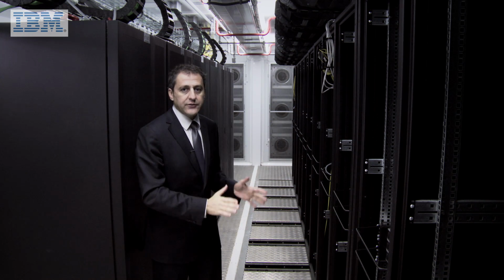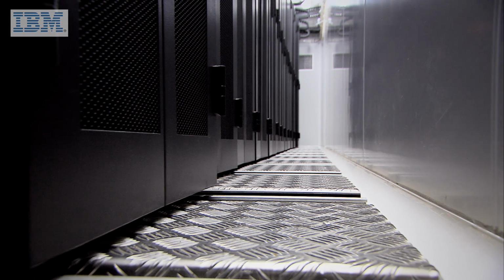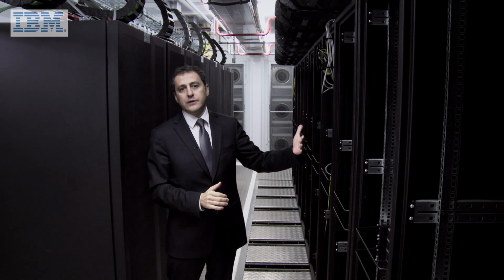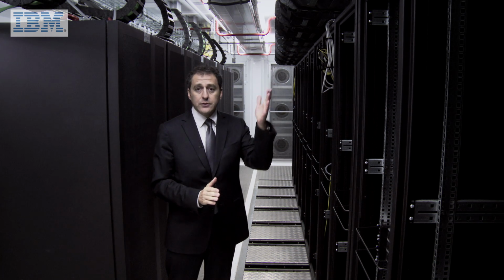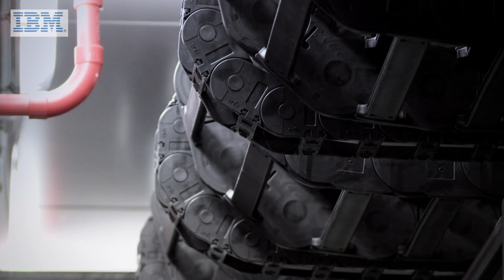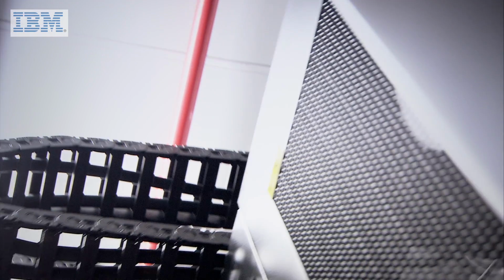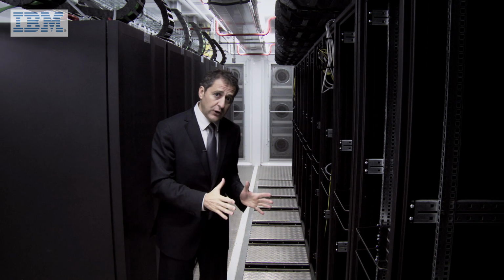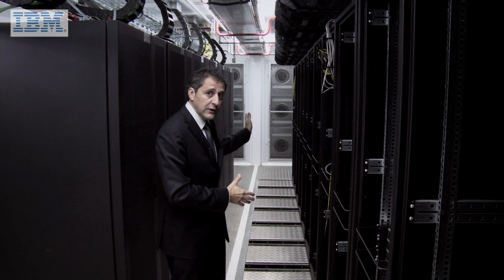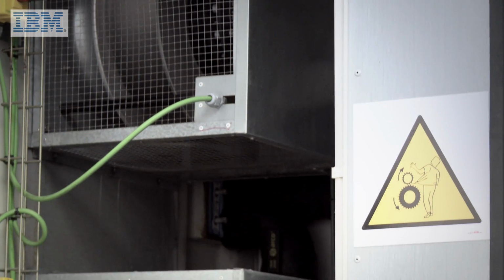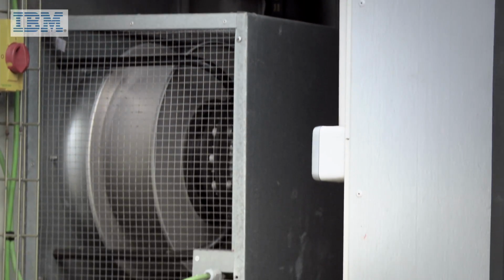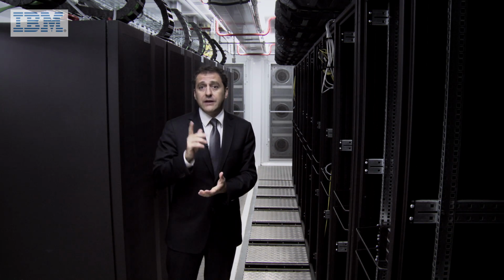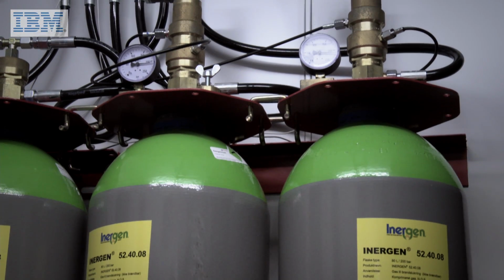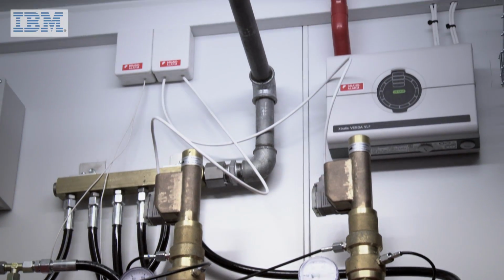You can realize this is a seamless join, and also that racks are placed on rails, which are very easy to move back and forth, and provide enough space for service either on the back side or on the front side when engineers are loading up servers or installing any machine. Also, power and data cables are managed through this flexible cable tray in order to avoid any sort of stress on the cables. And the hot air is collected by the natural free cooling system at the back end of this corridor in a separate module which is attached to the IT modules. Also, you may realize there is a VESDA very early detection system installed, as well as pressure sensors, temperature sensors, and relative humidity sensors.